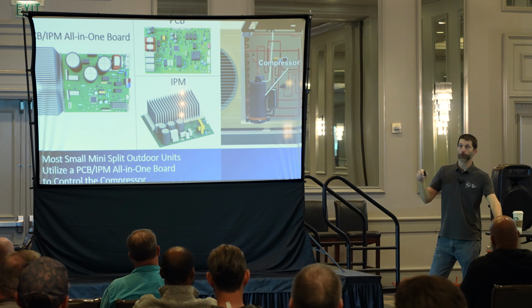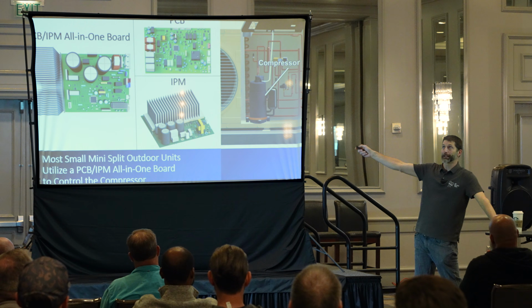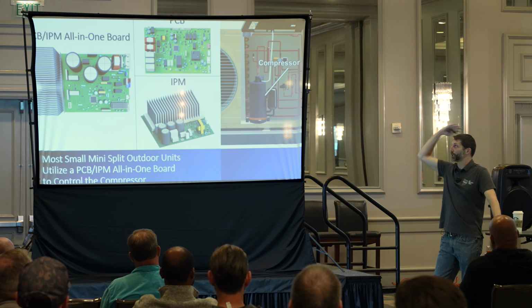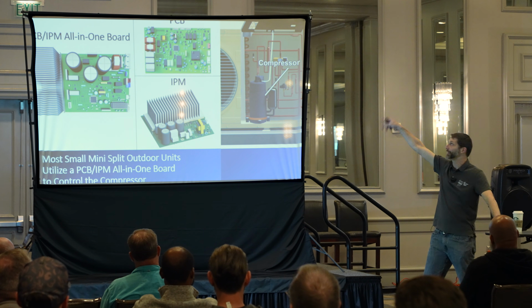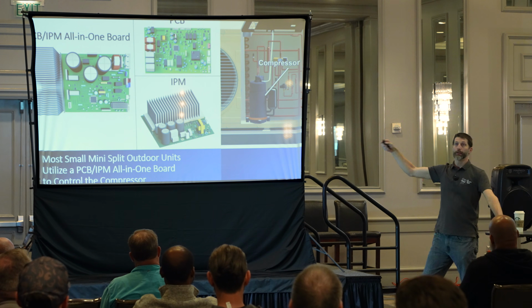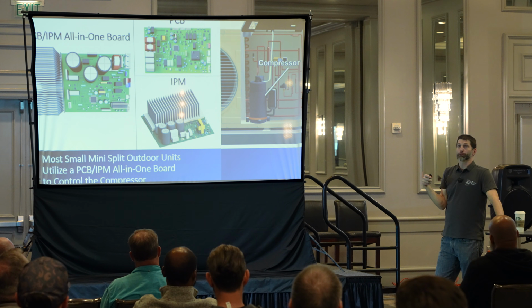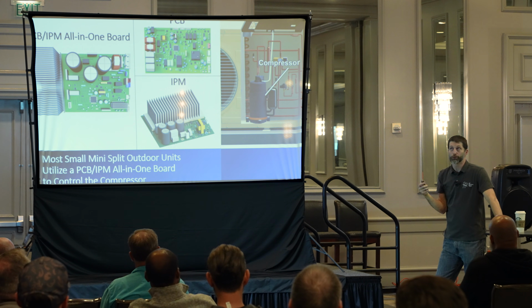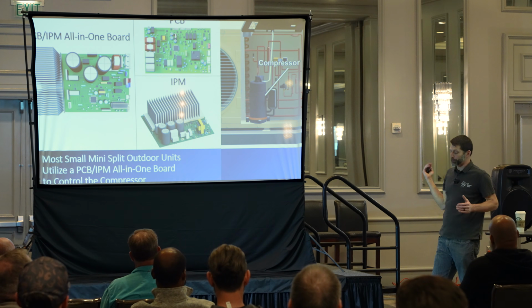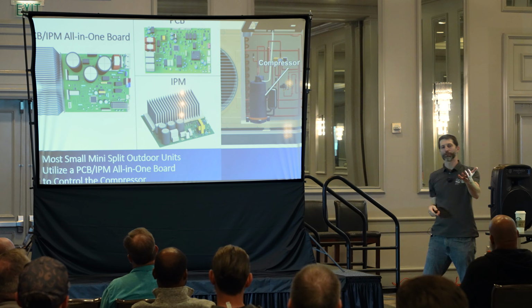And so if it's normally 240 volts and it goes up to like 260, it's going to cut the power off to the outdoor unit to save that circuit board. And then likewise, if it goes down to like 208 volts or something like that, it's going to cut off power to the outdoor unit so that, once again, it doesn't get damaged at the outdoor circuit board. Well, here's the other problem.